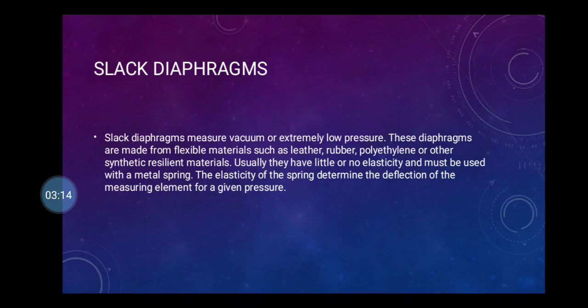The material used for a slack diaphragm is rubber or any other flexible material. The spring provided is weak. The large area can be used for pressure ranges 0.01 to 0.40 mm Hg (torr). The instrument has a high accuracy. Advantages of the diaphragm pressure transducer.